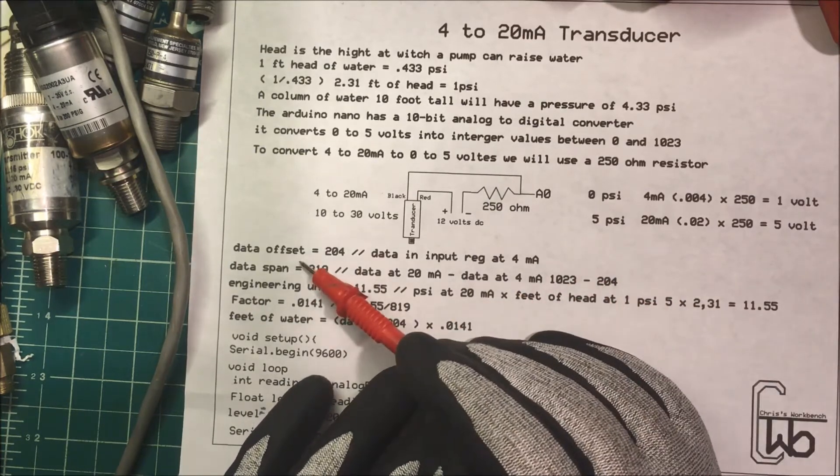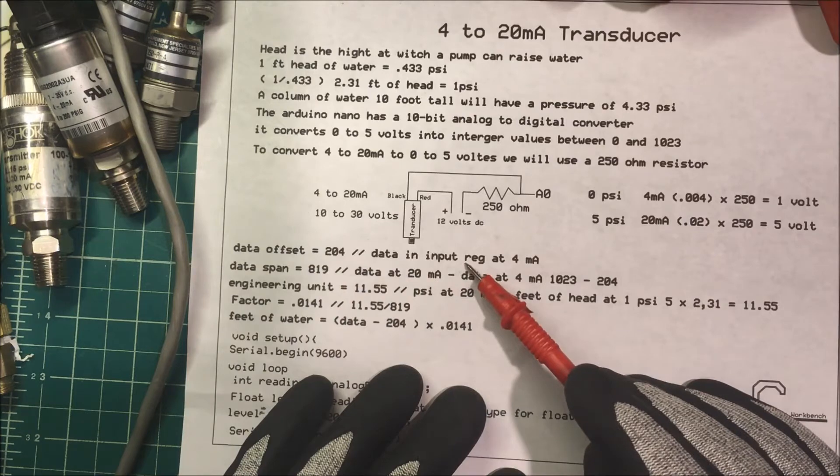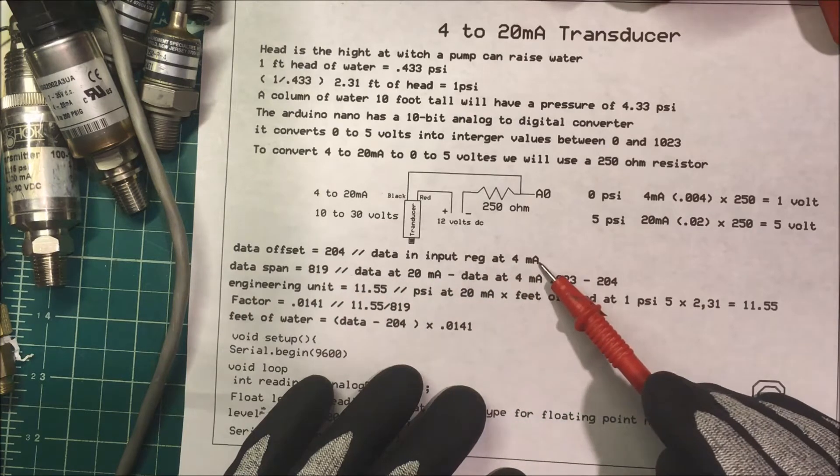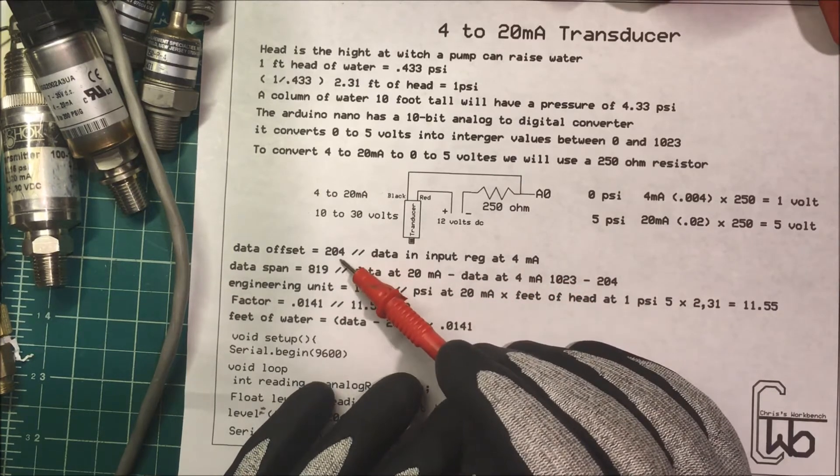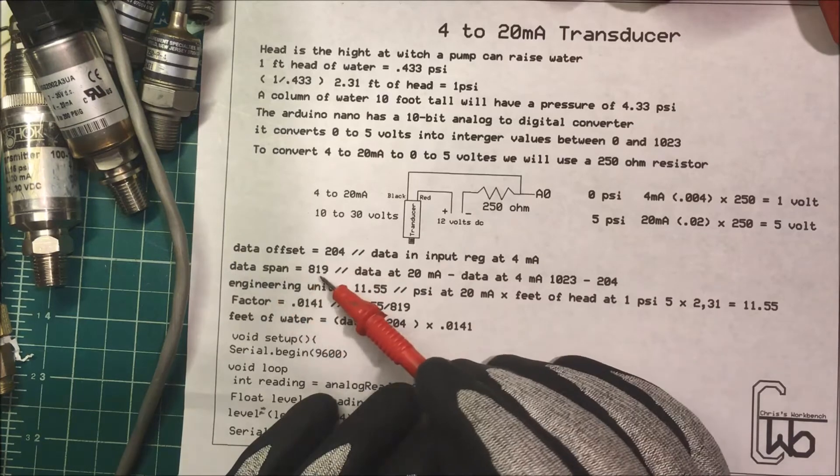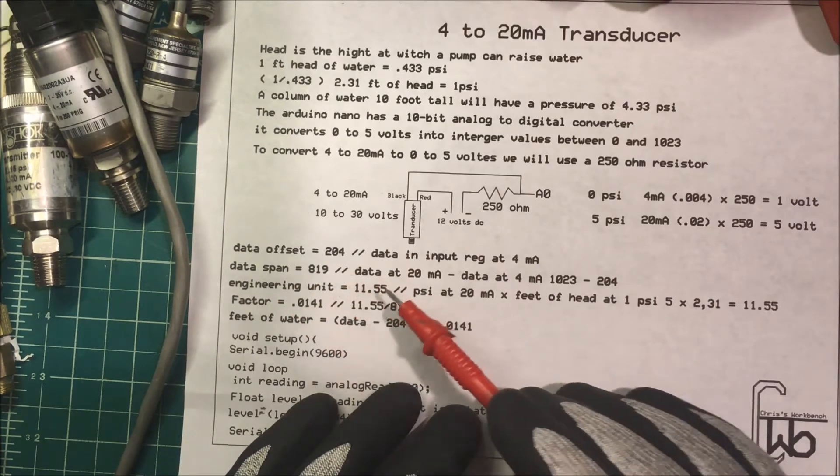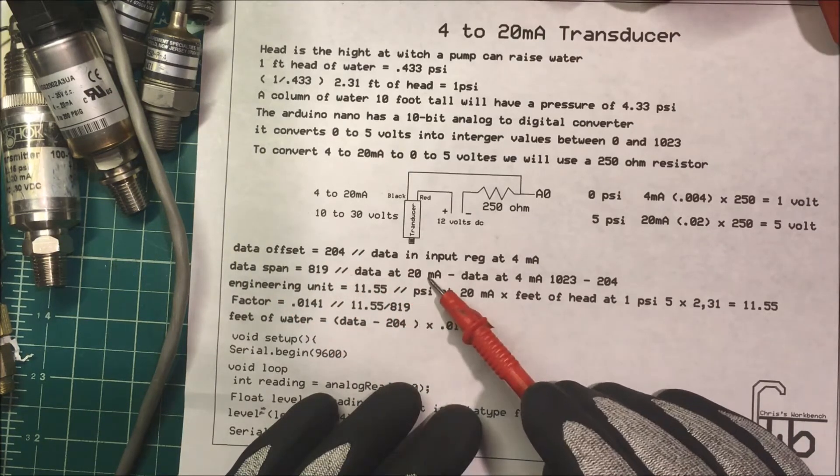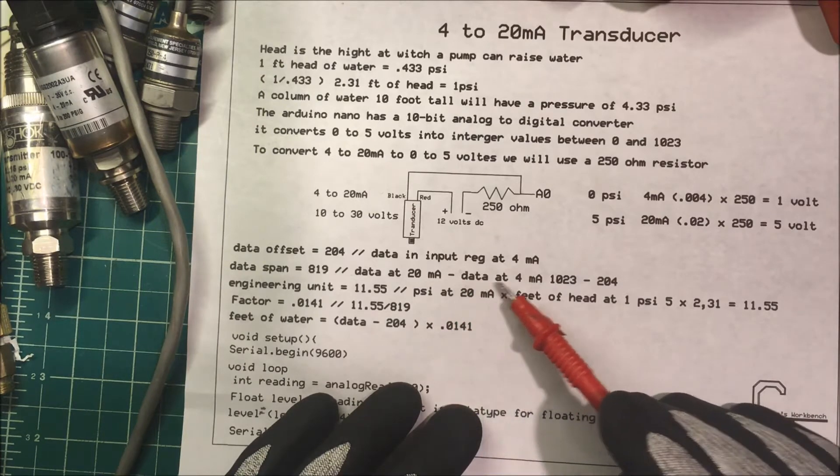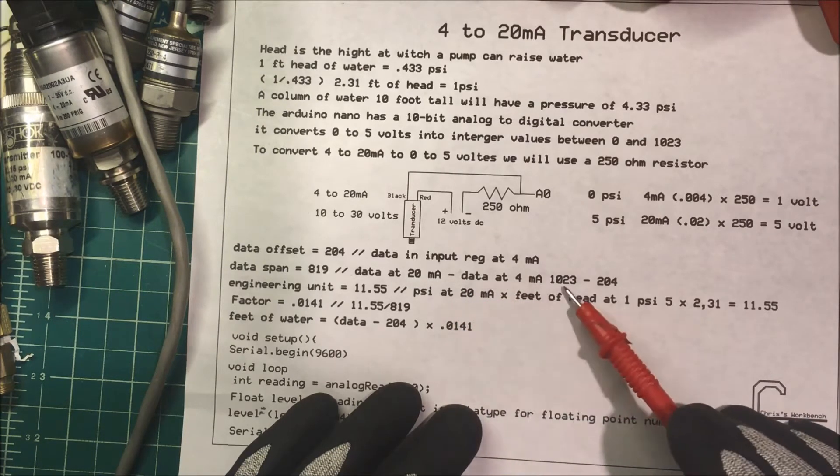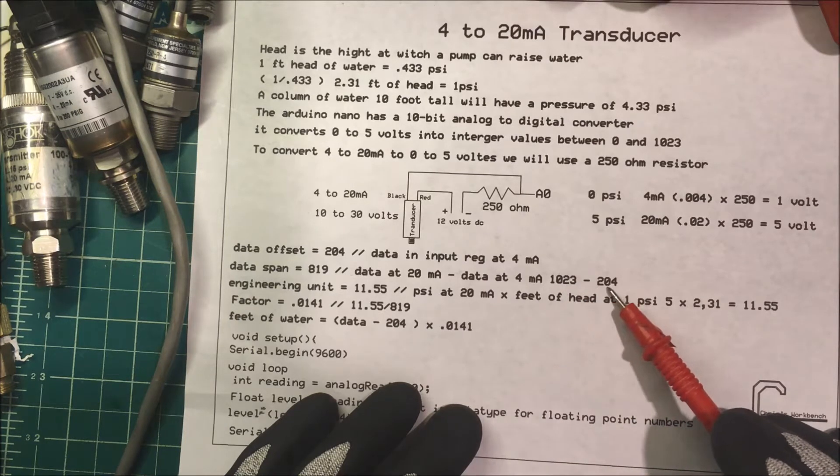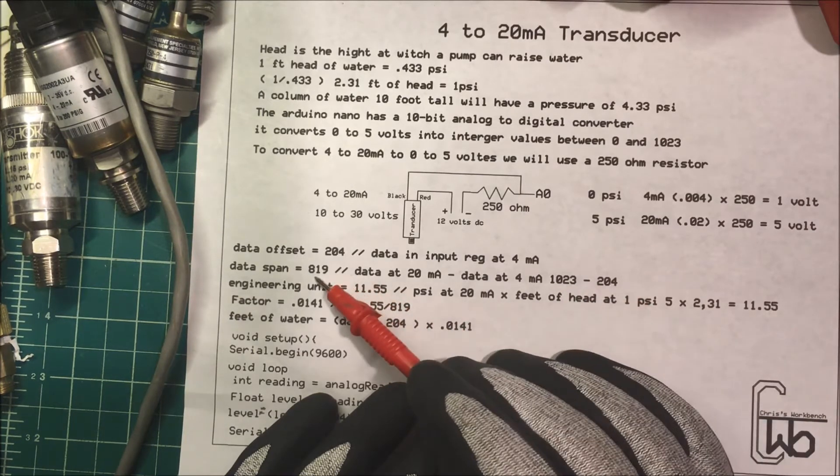So the data offset is just the data that's in the input register at 4 milliamps, and that's going to be 204. Now the data span is going to be 819, and that's just the data at 20 milliamps minus the data at 4 milliamps. So at 20 milliamps it's going to be 1023, and we subtract 204 from that and we get our data span.